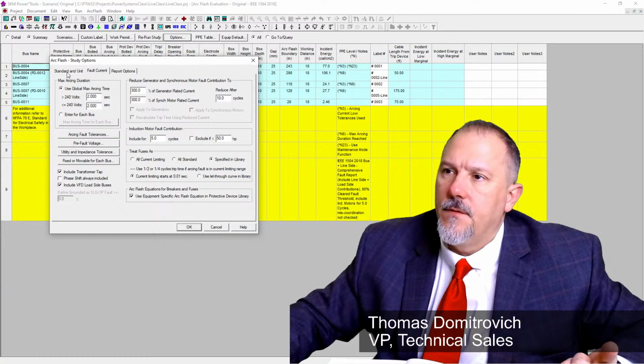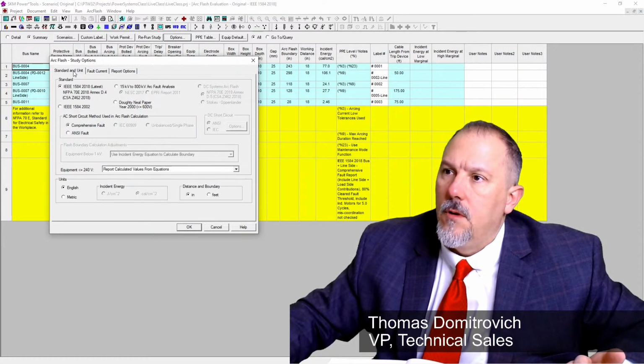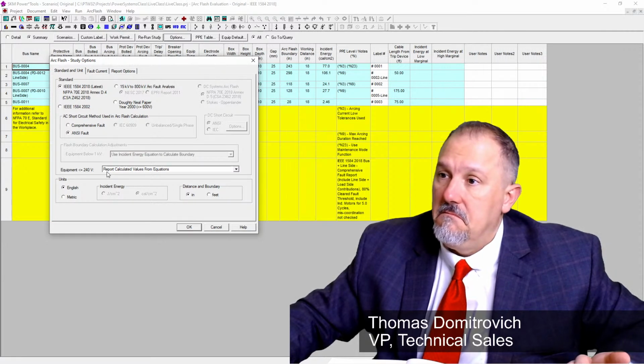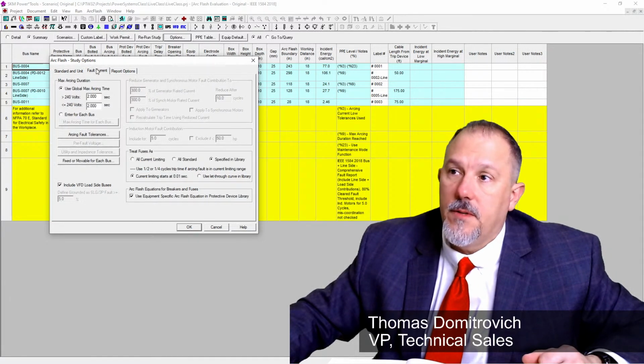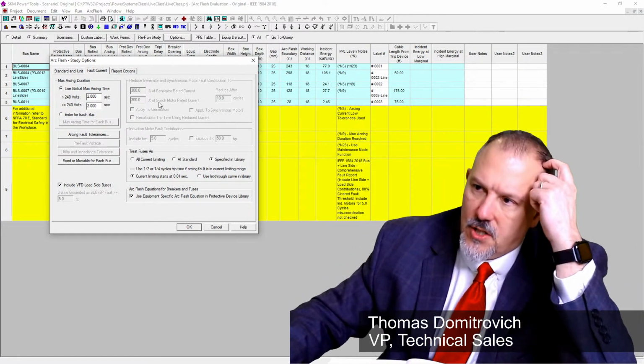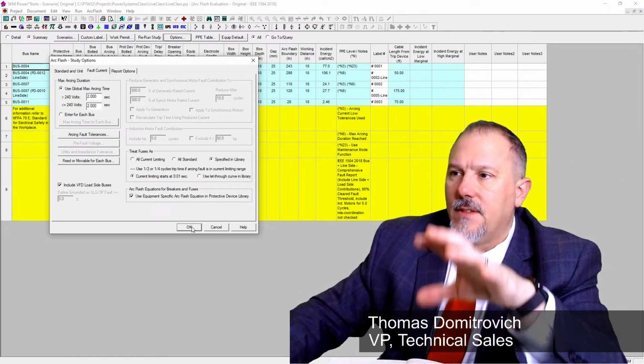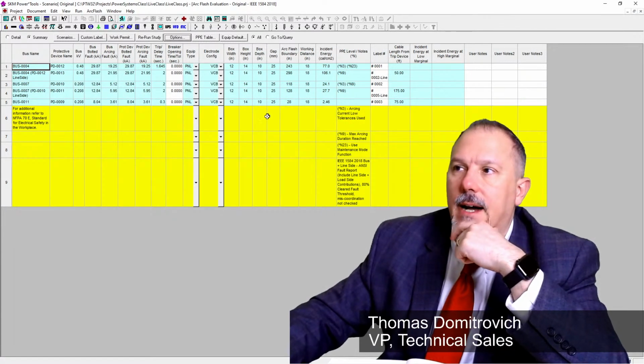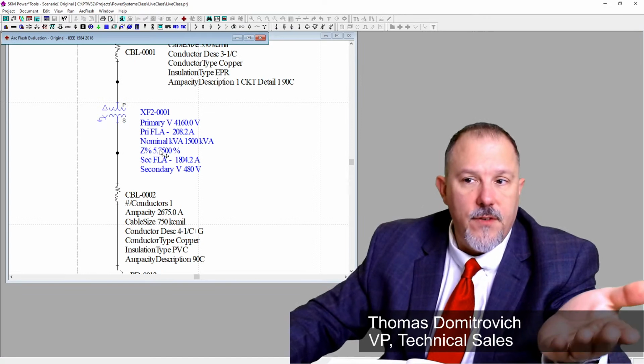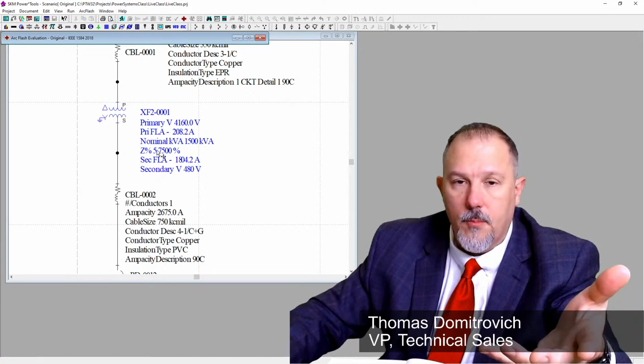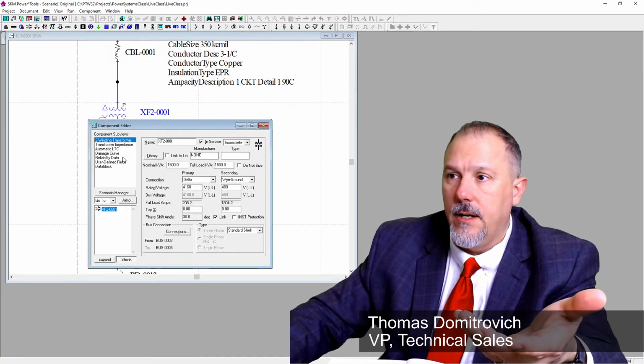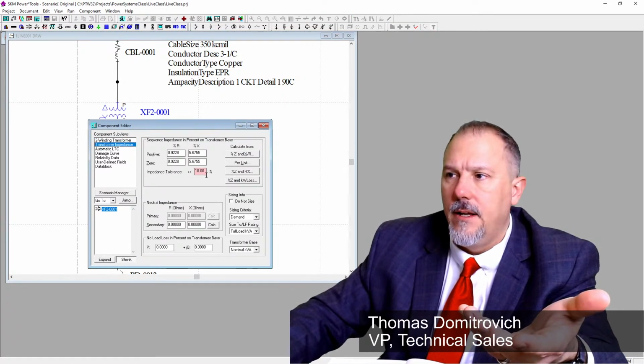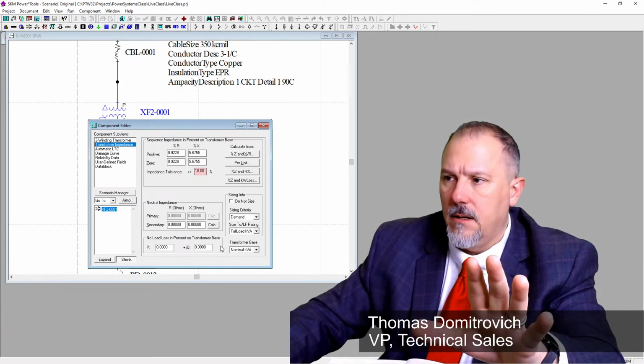I don't see anything in here for, what was that? No. ANSI, I can use the ANSI process, English. No, I don't see where it counts for it. So you may have to manually, I'll have to do some research. When we get into the arc flash and whatnot, I'll have to do some research to see how SKM, and if you have a tool that you use, how do they incorporate the plus or minus for the transformers and whatnot. So transformer impedance, I would have thought that this thing would use. I'm probably just missing something in here.